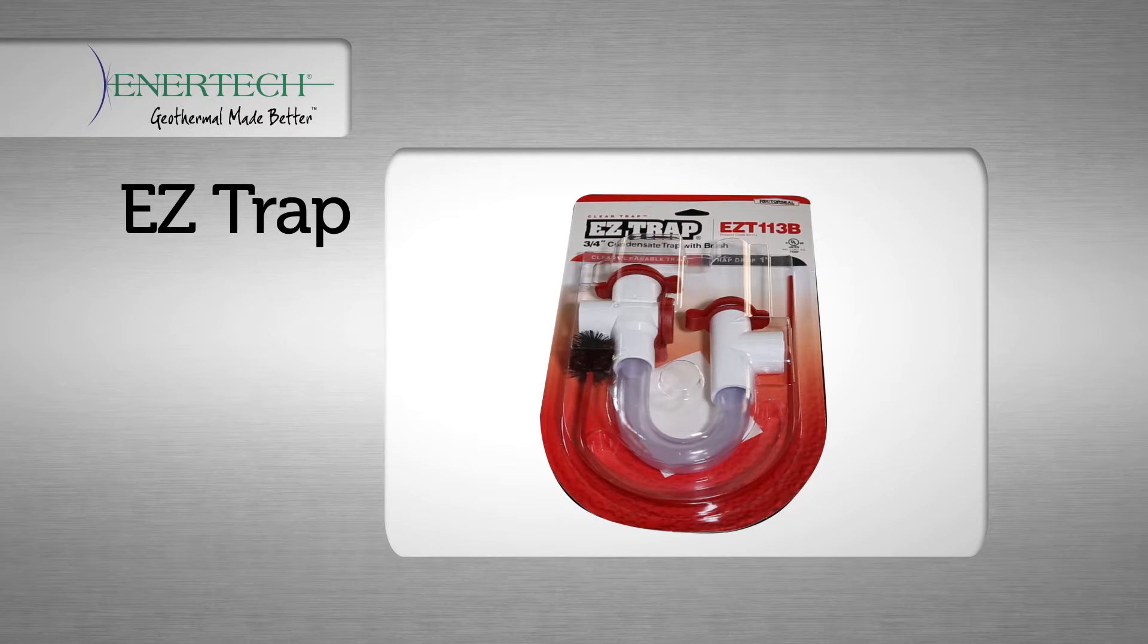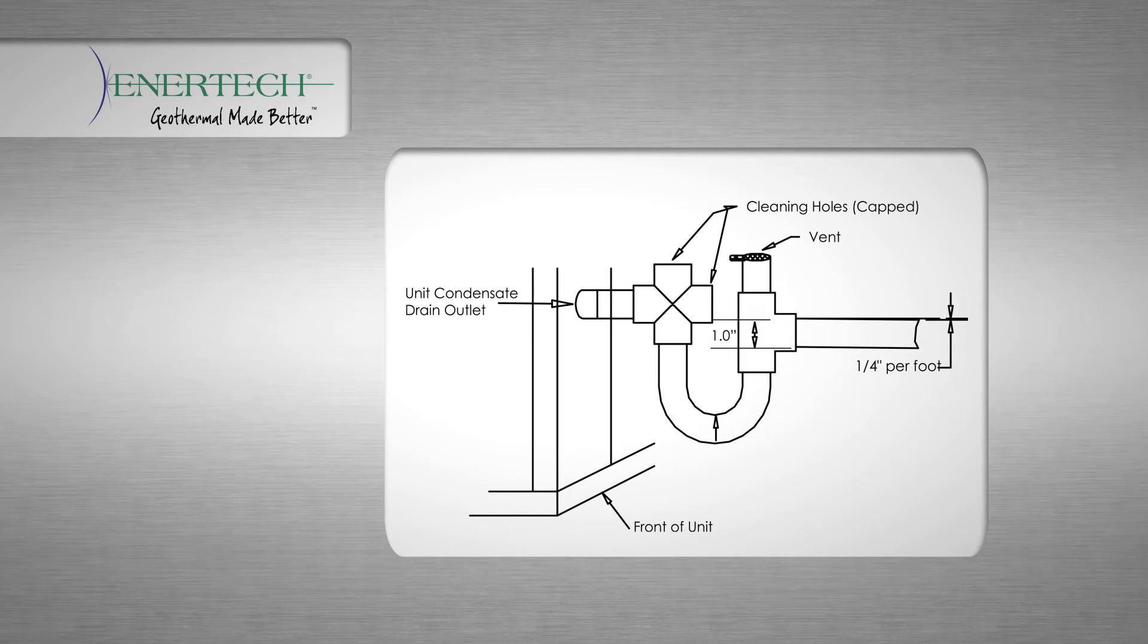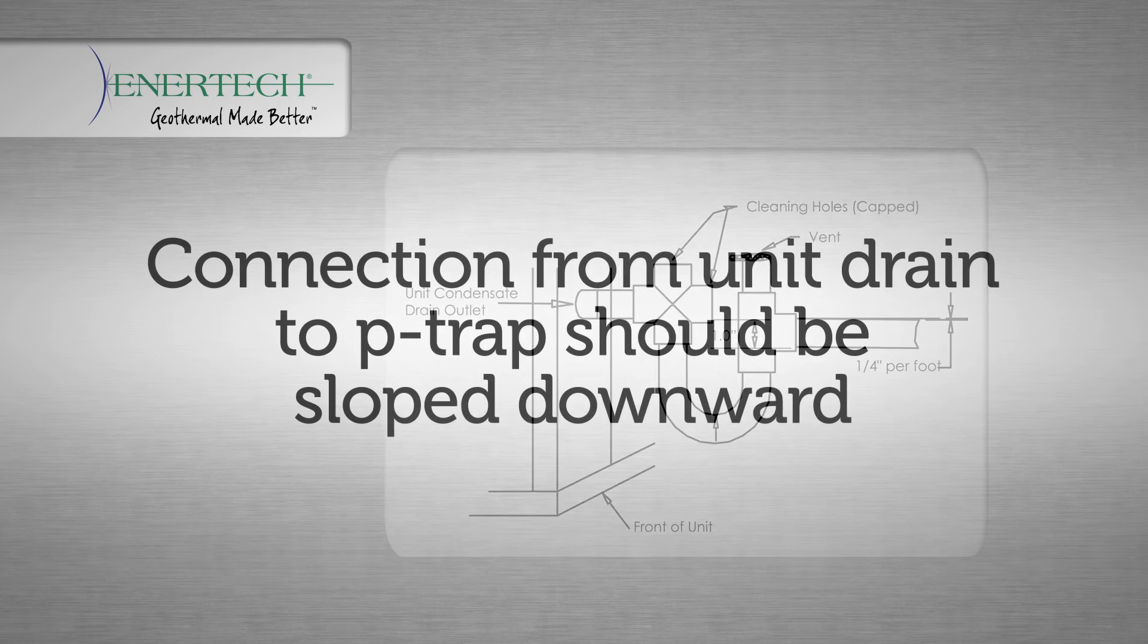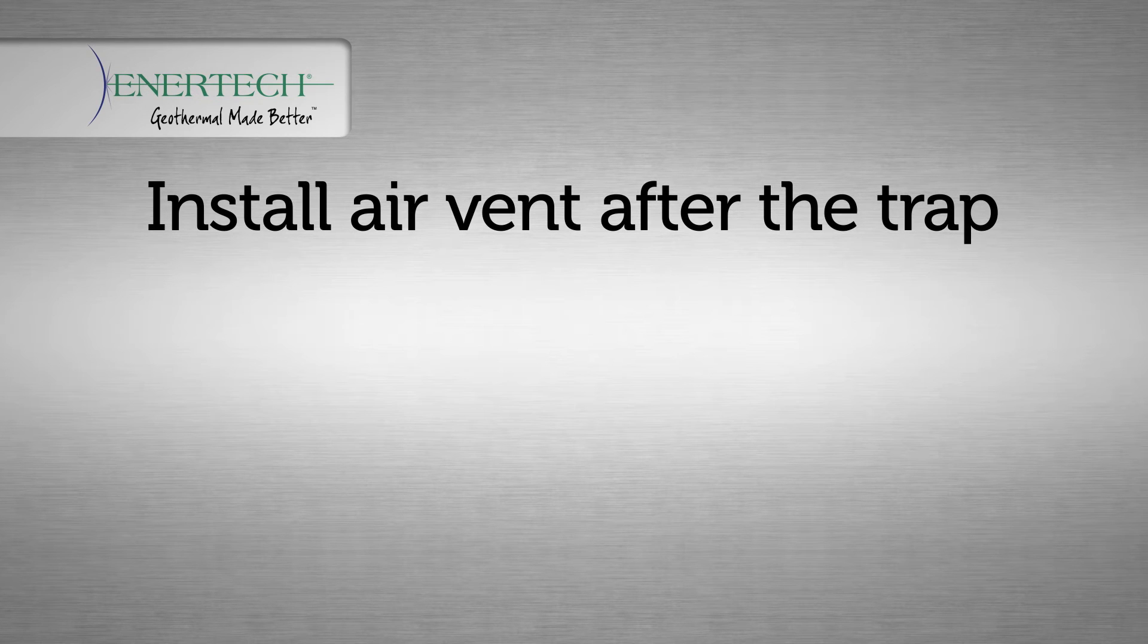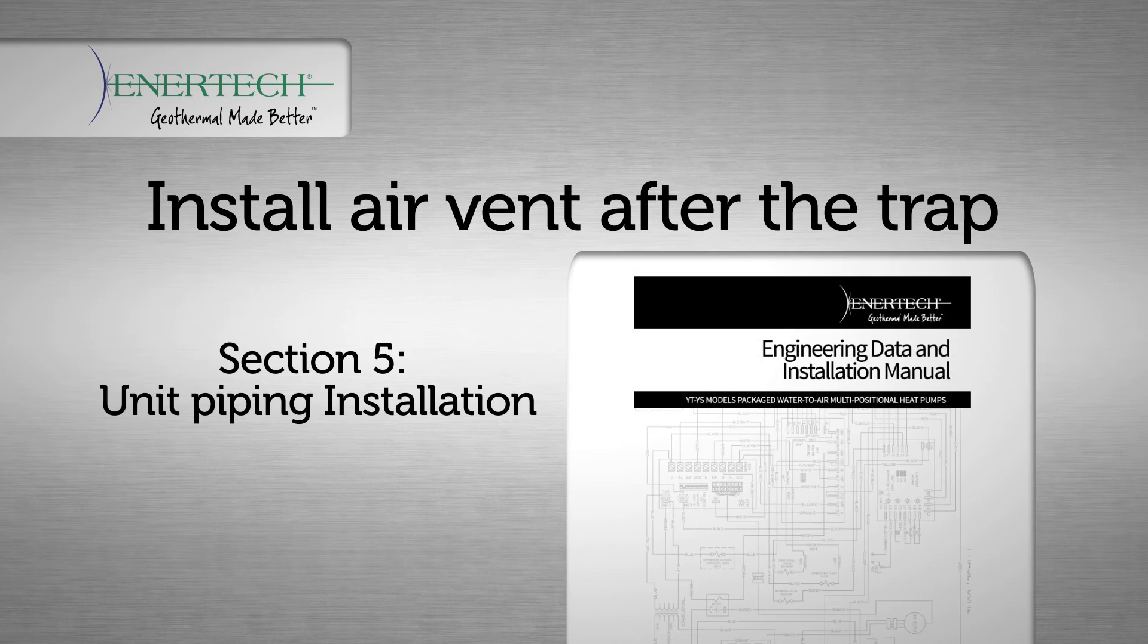Complete the drain installation by connecting a P-trap to the equipment condensate drain connection. The condensate line must be trapped a minimum of one inch as shown in the diagram. The condensate line should be pitched away from the unit a minimum of one quarter inch per foot. The condensate line from the unit drain connection to the P-trap should be sloped downward. Always install the air vent after the trap.